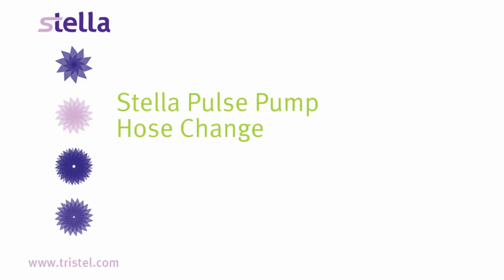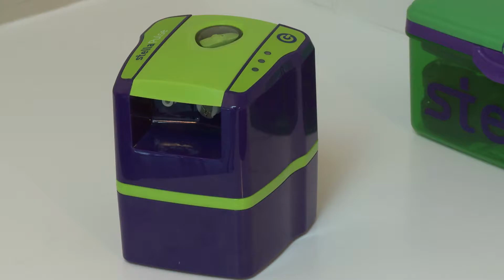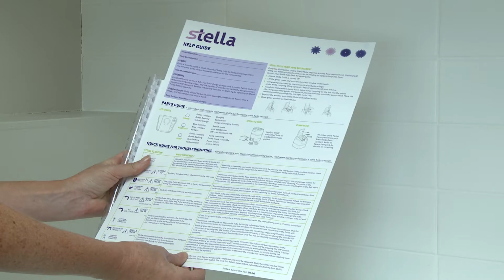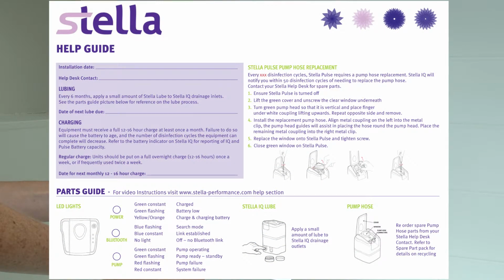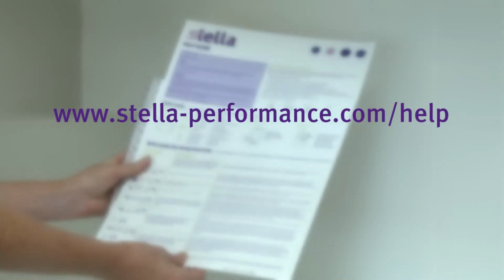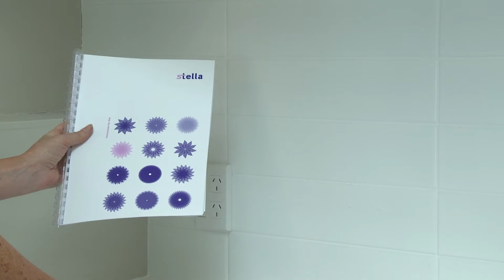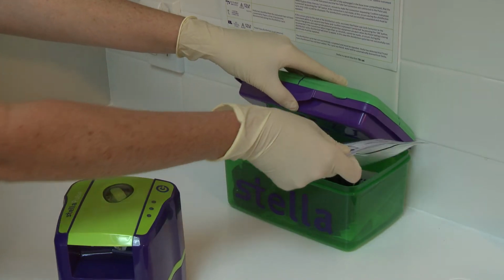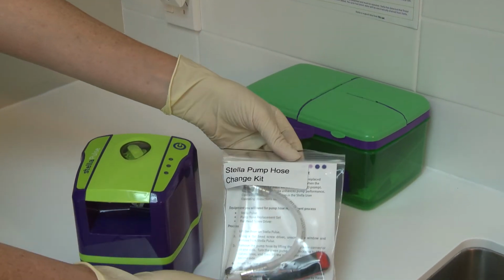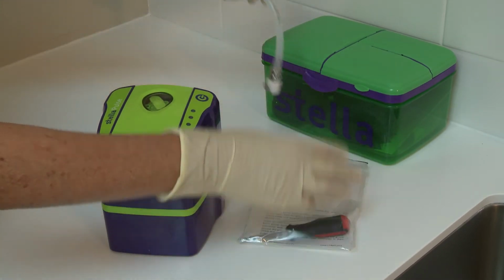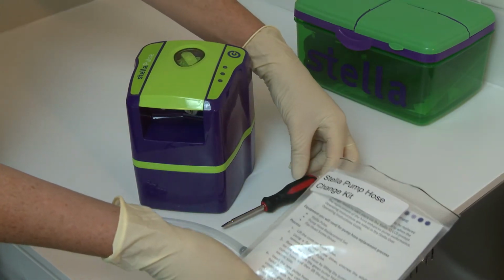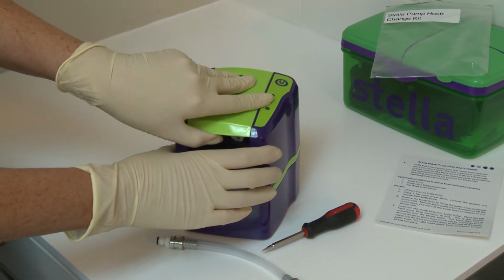Stella Pulse pump hose change. Stella Pulse requires a pump hose change every 1,000 disinfection cycles to assist the performance of the pump. Instructions for the pump hose can be found on the Stella Help Guide wall chart, on the Stella Performance website, and in the Instructions for Use manual. A pump hose change kit with instructions, spare pump hose part, and screwdriver can be found in your Stella toolbox. The change process is as follows.